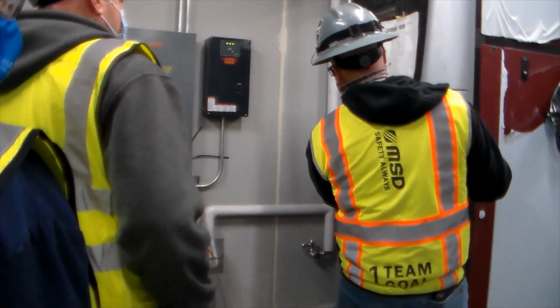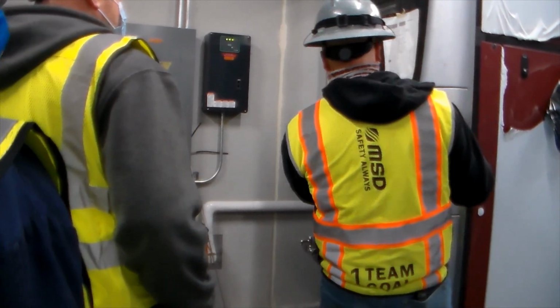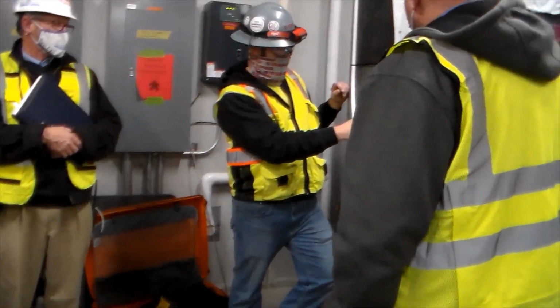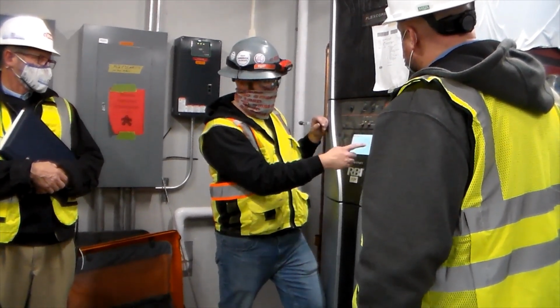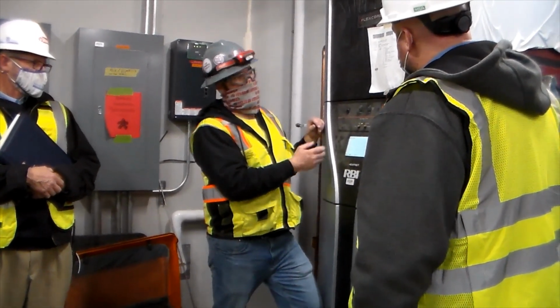You can actually dig deeper and go to each boiler. This is the master boiler. See the set points, the percentages modulating that. And you go through your outdoor temp, header, supply and return temp, and the status with all your switches and what is actually running. If it's failed, it will be in red.